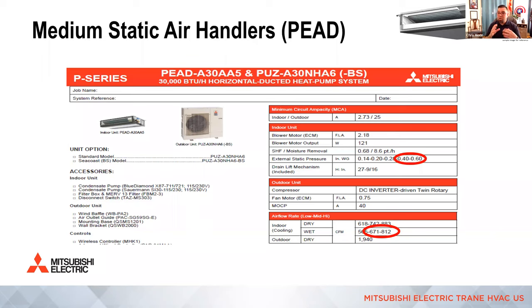All right, so the next one I just want to talk about, a lot of the same rules apply on layout when it comes to a PEAD, which is our mid-static air handler. The mid-static air handlers actually ship at 0.40 inches of water column to start your external static pressure. And this is the submittal taken right off of mylinkdrive.com. And you can see the volume of air that is associated with those external static pressures.